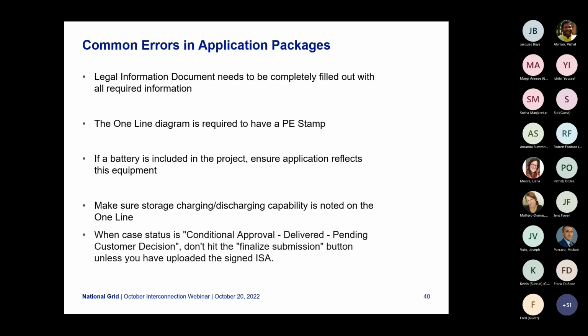Some common errors that we've seen in application packages that hopefully we can highlight and cut down on. The legal information document quite often is submitted without being completely filled out. We do need that completely filled out. The one-line diagram is required to have an electrical PE stamp. If there is a battery included in the project, we want to ensure that the application reflects this equipment. Again, as noted earlier, we want to make sure that the storage, charging, and discharging capability note is on the one-line diagram. And just a reminder, when your case status is in conditional approval delivered pending customer decision, meaning we have issued the ISA, please don't hit the finalize submission button in the portal unless you have uploaded the signed ISA. Next slide, please.